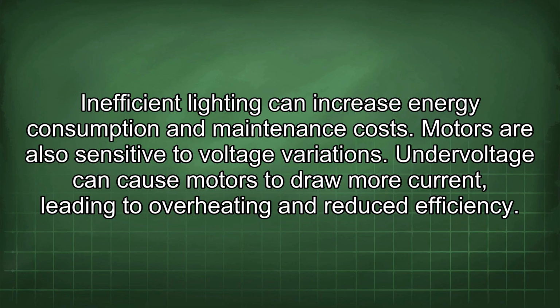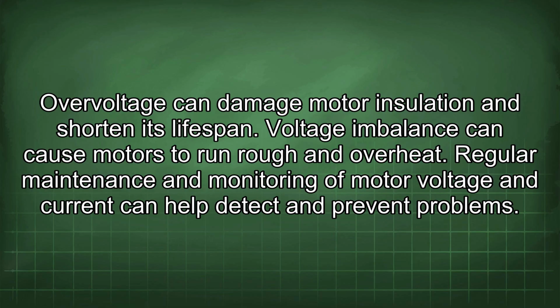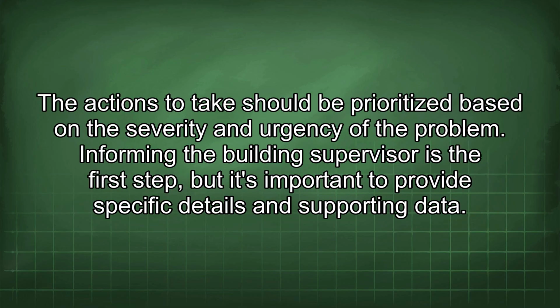Motors are also sensitive to voltage variations. Undervoltage can cause motors to draw more current, leading to overheating and reduced efficiency. Overvoltage can damage motor insulation and shorten its lifespan. Voltage imbalance can cause motors to run rough and overheat. Regular maintenance and monitoring of motor voltage and current can help detect and prevent problems. The actions to take should be prioritized based on the severity and urgency of the problem.